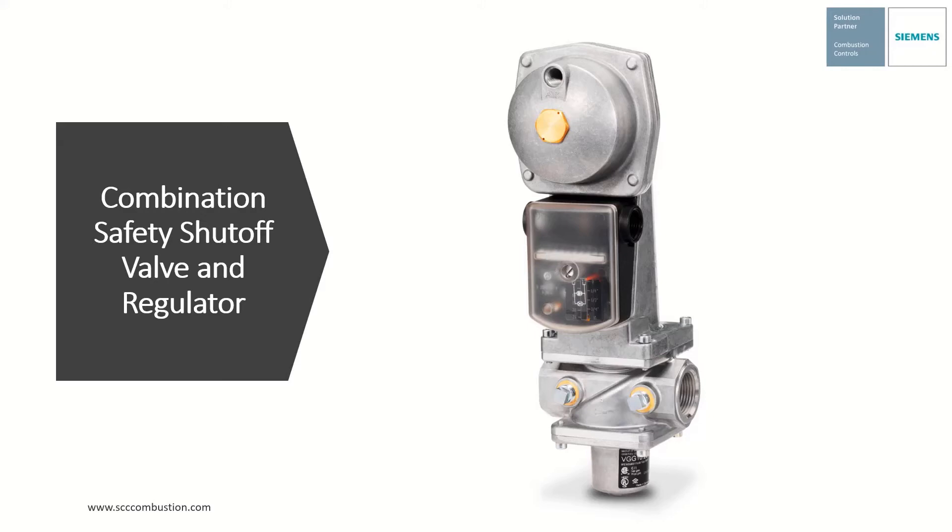With the SKP25, the safety shutoff valve body is the orifice of the regulator. We need to think about the valve body size like we would think about an orifice of a regulator.